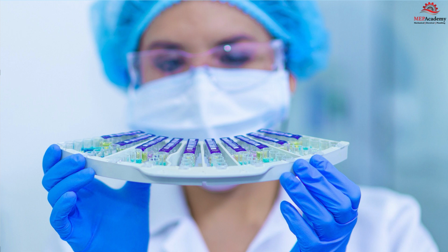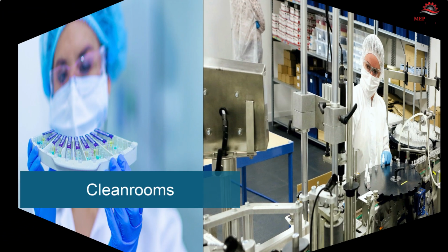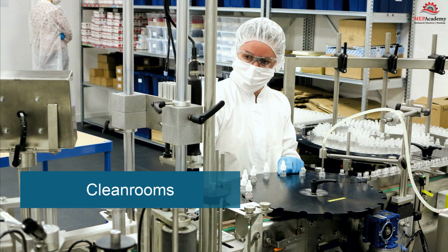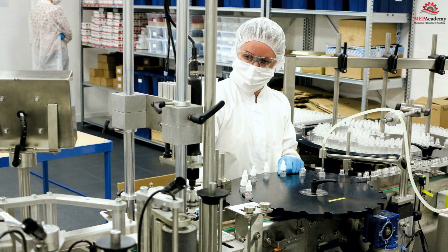Fan filter units are commonly used in various types of rooms and environments that require a controlled level of cleanliness. Here are some examples. Clean rooms. FFUs are extensively used in clean rooms across industries such as pharmaceuticals, electronics, biotechnology, healthcare, and semiconductor manufacturing. Clean rooms maintain low levels of airborne particles to protect sensitive processes, products, or research. FFUs are often installed in a ceiling grid system of clean rooms to provide a constant supply of clean, filtered air.